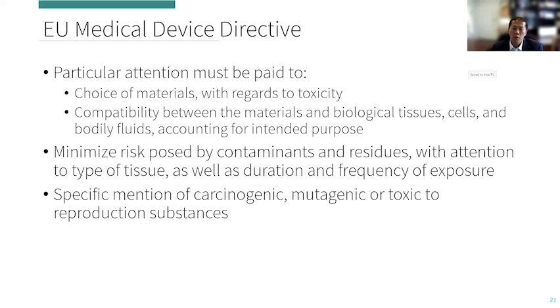So this is very similar to what we saw earlier with the FDA tripartite guidance, where we talk about the different categories of devices. Although we saw earlier that the ISO 10993 standard came about and was published in 1992, the EU Medical Device Directive, which came a year later, makes no explicit mention of the ISO standard.